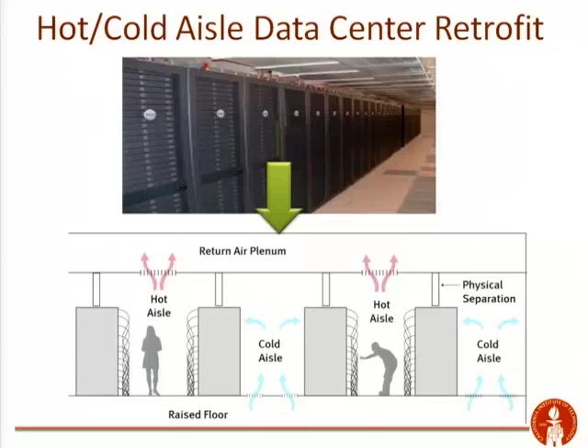What we've done is physically segregate the hot aisle and cold aisle, so the servers only need cold air on their front end. They exhaust hot air on the back end, so there's no point cooling the back end of the servers. We physically separate those, only providing cooling on the front end where it's needed, giving us significant savings just from a physical design perspective.